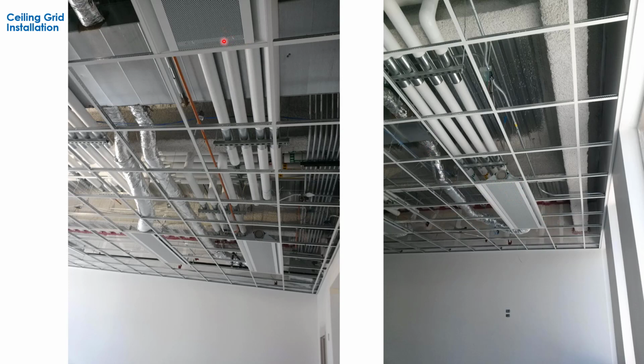Here's another example of a chilled beam at the top of the picture. Again, you can see the water lines coming over. There's more ceiling plenum space in this, but it's still pretty tight when you're passing underneath the ductwork to get the beams all over. And remember that chill beams are dry devices, so there is no condensate pan and no condensate piping to these things. It's just 2-pipe or 4-pipe water supply to the beams.